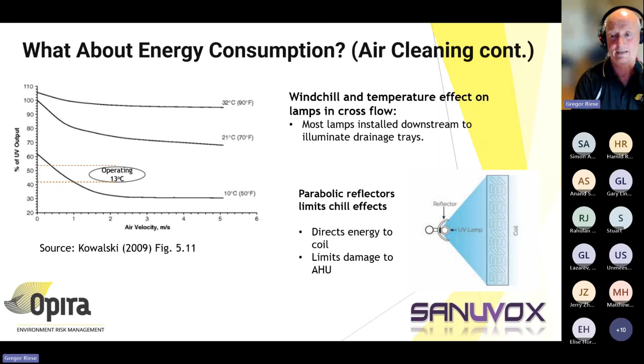So a point of difference in terms of the Sanuvox product is that they always sell the coil cleaning product with a parabolic reflector. It's made out of brushed aluminium and reflects most of the light, like 80% of the light, back towards the coil. Again, if you think about the front of a lamp, imagine jumping into an air handler downstream of a cooling coil with glasses on. It gets fogged up very quickly. The reflector is really important to make sure the energy goes forward and disinfects the coil.